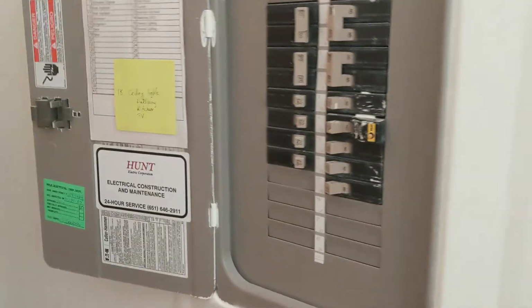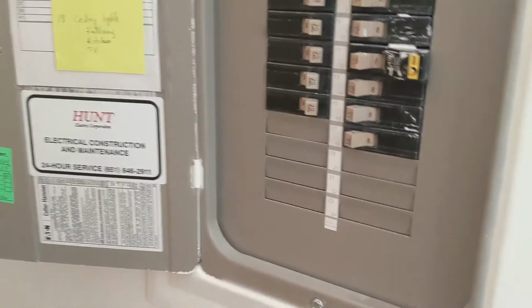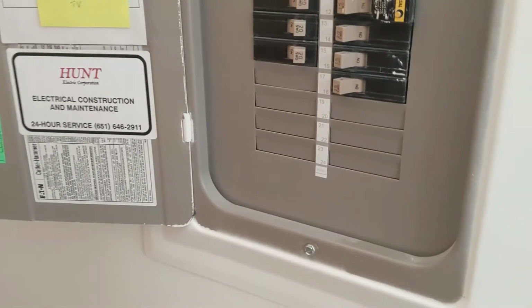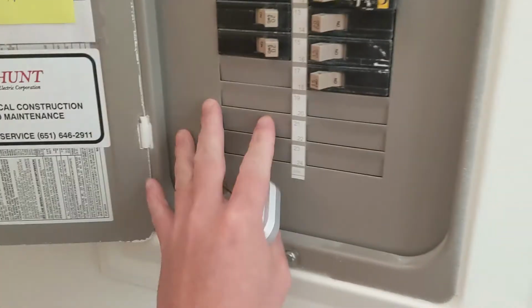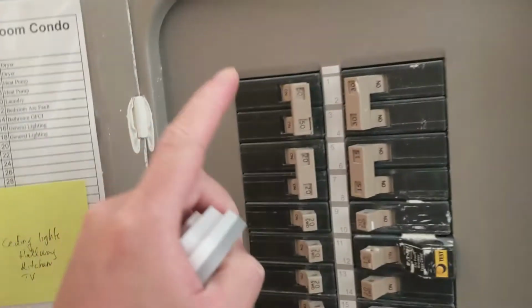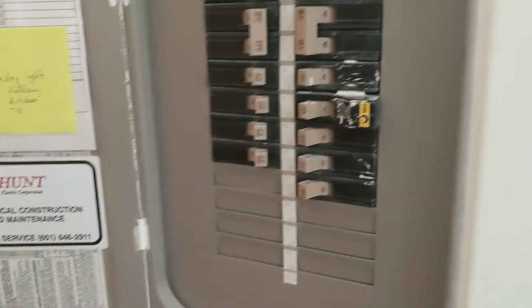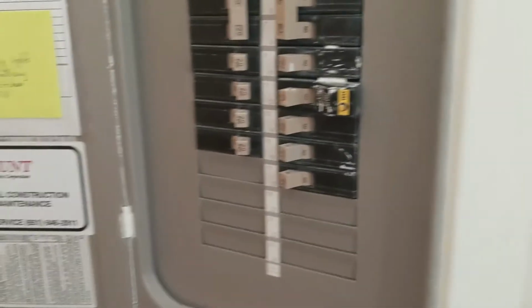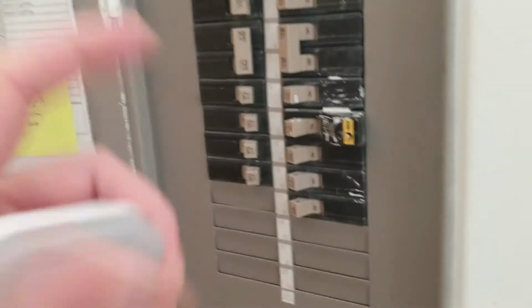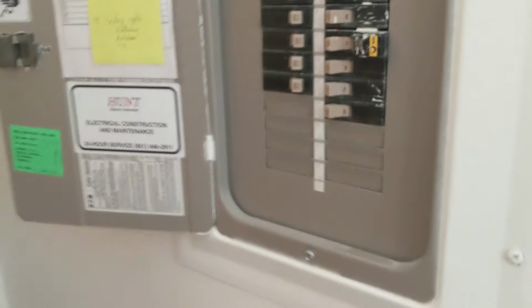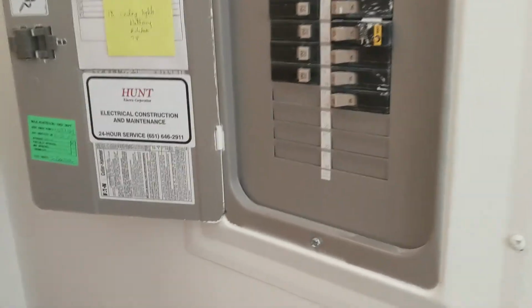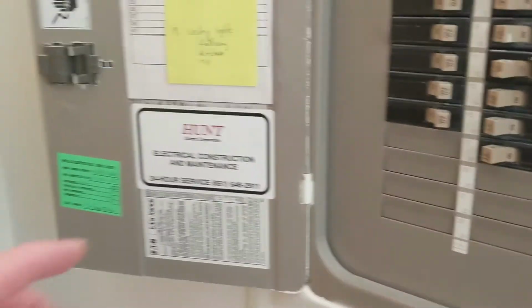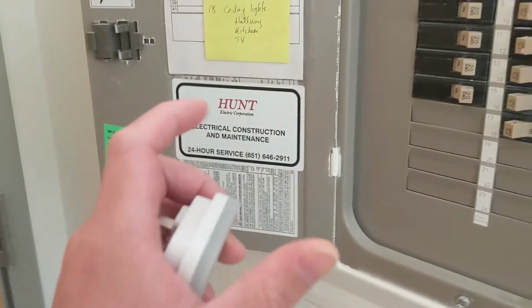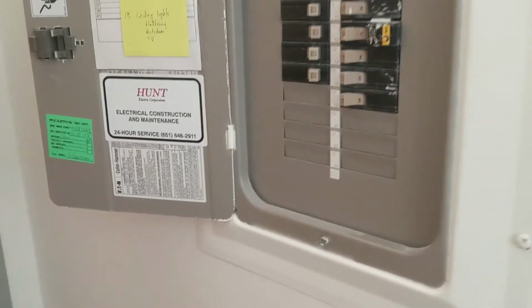I like to go from the top down, and I use the rule of 80. You're going to hear that a lot. I only want to consume 80% of my breakers. I only want to consume 80% of each circuit. I only want to consume 80% of each outlet. And I only want to consume 80% of each PSU. The reason being is I don't want to short anything. I don't want to burn anything. I want to have that capacity because with mining, as you know, sometimes it fluctuates, right?